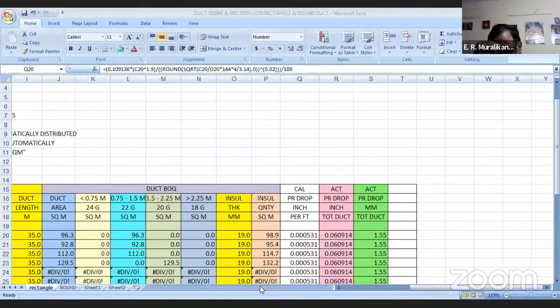See, that's what I told you a few minutes back in the discussion, when you have to demand the fan selection from the fan person or AHU person. As long as the fan RPM is very close to the motor RPM, the motor being 2 pole, 4 pole, 6 pole, 8 pole, you can go for a smaller pulley and your friction and belt losses are less. Suppose your fan RPM is 930 and you go with 1440 RPM, the belt loss will automatically accumulate for that speed reduction. But instead of 960 RPM, if the fan is 930 RPM, very close, the belt loss is small, and you can run at 960 also, no harm in that. So it all depends: if you demand the fan selection from the supplier and choose the correct motor, it will be fine. Otherwise, it's not possible.